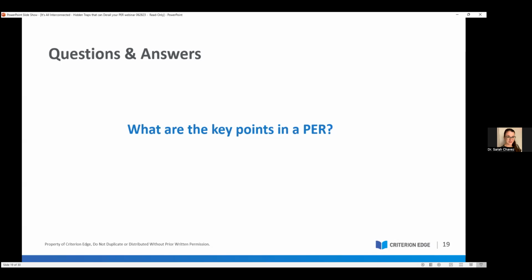Or are there circumstances or locations or environments where it's not as accurate? So that's the clinical data. But you have to tie all of that together and support it with the state of the art. And really, that's why we think the scientific validity report is so important in this case. It's because the scientific validity shows the association of what you're looking for with the diseases you're claiming you're indicated for diagnosing. So are you looking for the right analyte to make that particular assertion?